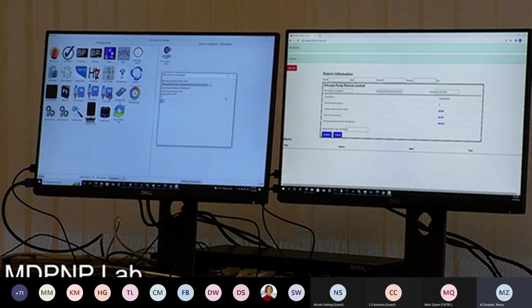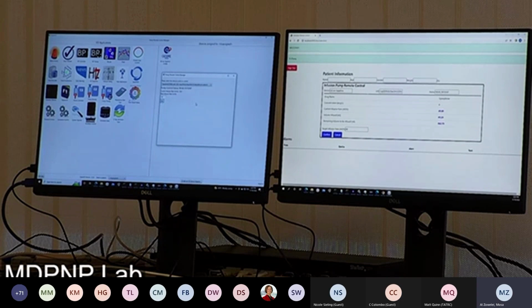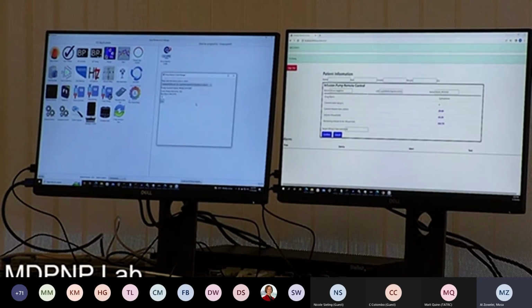Now, because the bedside user has ultimate control, we can go back here on the bedside computer, type in either that rate of 30 again or a new rate, and set the pump. So we'll change it to 20 and set. And there's no confirmation. We don't require the remote user to authorize the local user's commands. It's only when the remote user starts to issue commands. We want to make sure that the bedside provider knows who it is who's making those requests and explicitly authorizes that. The local user can always use this interface to change the pump without requiring external permission.